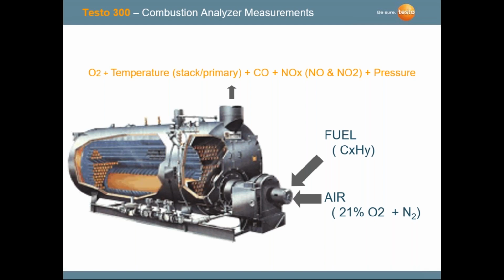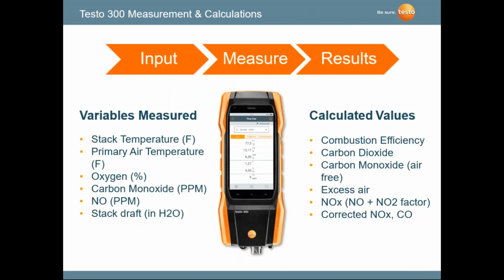If you're doing just boiler testing and NOx, and you just want a better than good ballpark reading, the 300 certainly is the instrument of choice when we're looking at NOx, again measuring NO and factoring in the NO2. Just wanted to bring that to everybody's attention. With the 300, we're measuring stack temperature, primary air temperature, percent oxygen, ppm carbon monoxide, ppm NO, and the stack draft is measured in positive or negative inches of water column. And we're also calculating combustion efficiency.